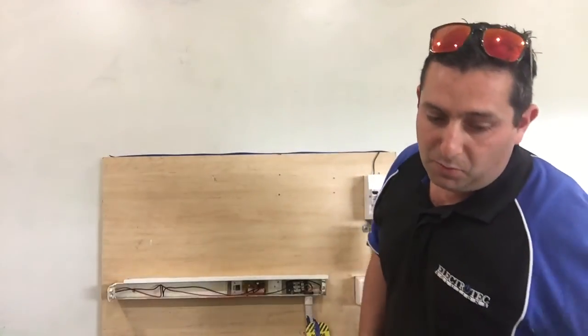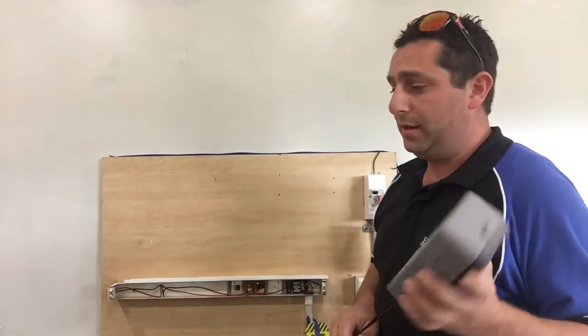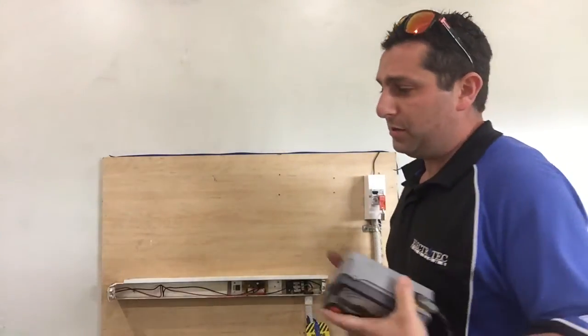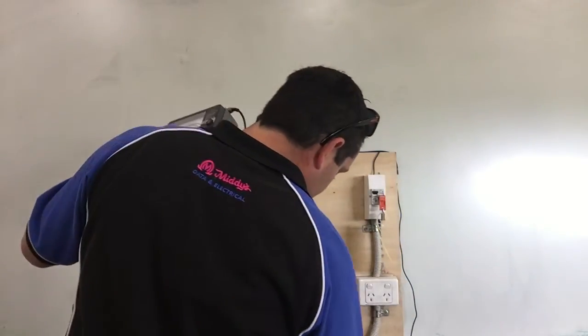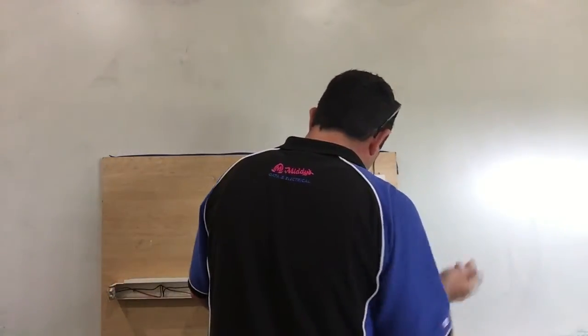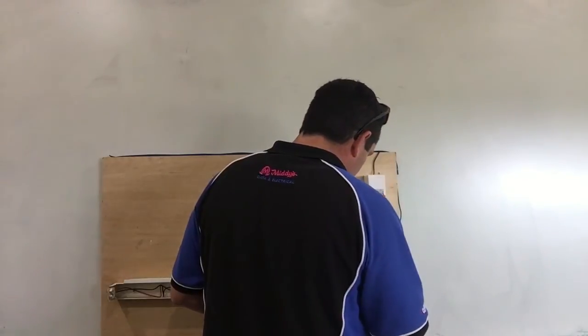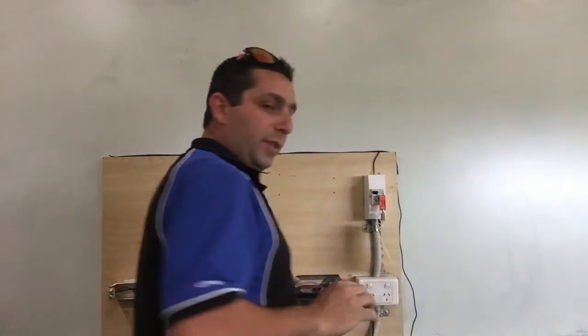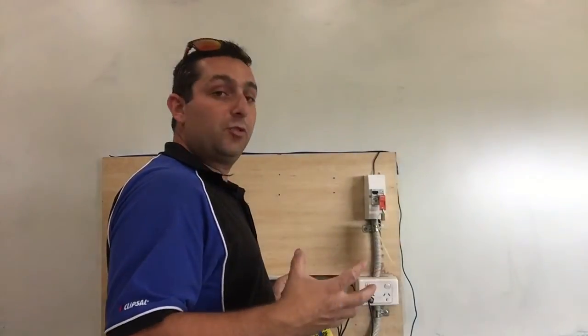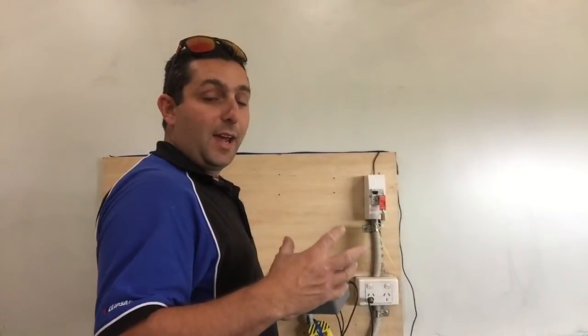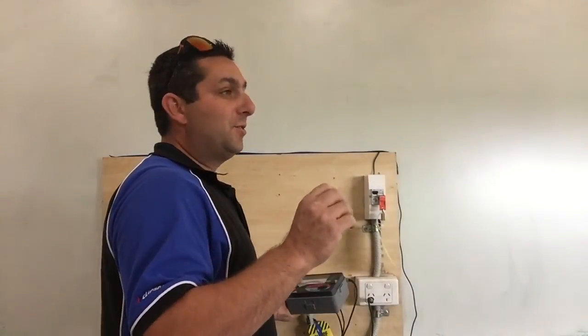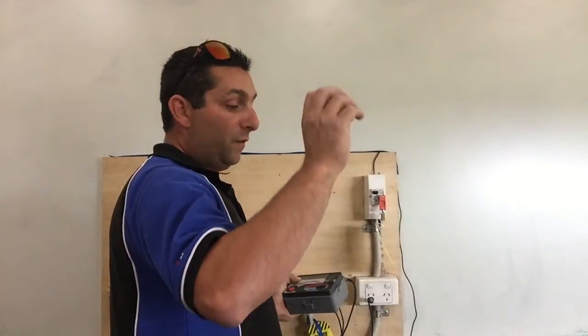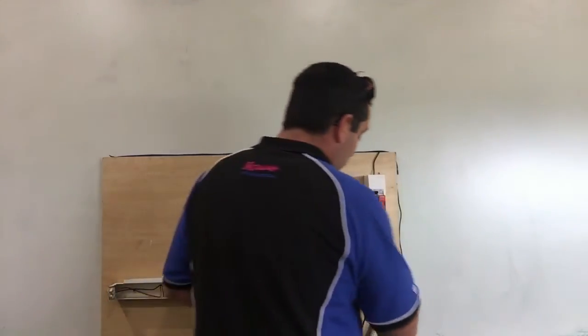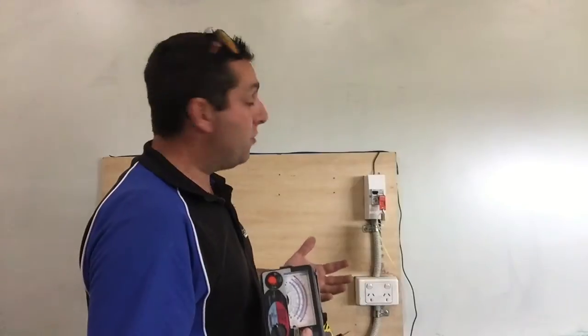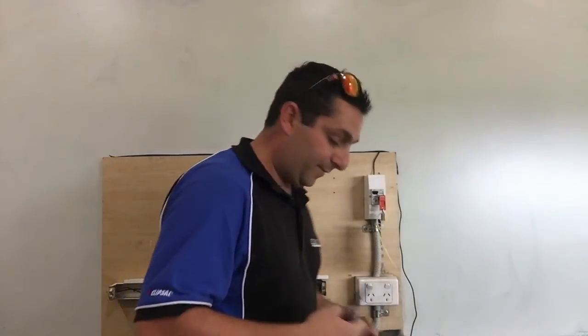Now that we've done that, we also want to test our protective earth, and that it is now connected to the greater mass of earth. So using again our trailing lead or our known earth, we want to test from the appliance to our known earth. Okay, we'll test that. We want that to be as close to 0 as possible. Really, it should be 0. But there is a table in AS 3000, table 8.2. If you go to your R of your earth, or your resistance of your earth, it'll give you the maximum allowable ohms according to the breaker size and the cable size. I've established that that is fine.